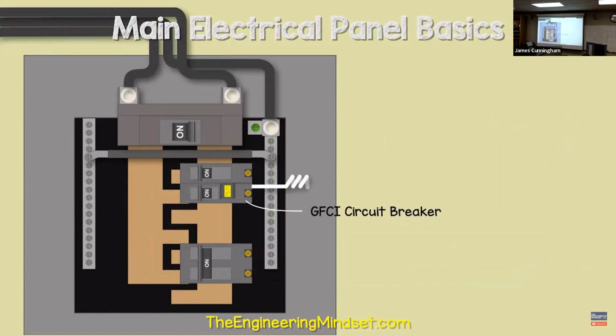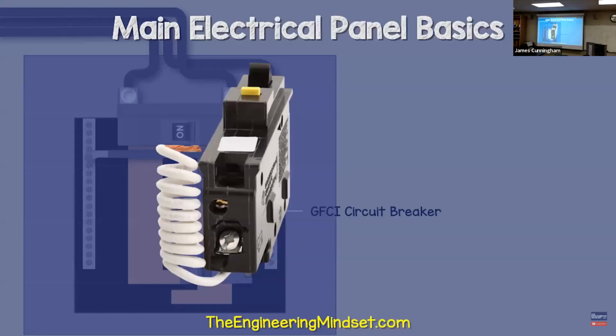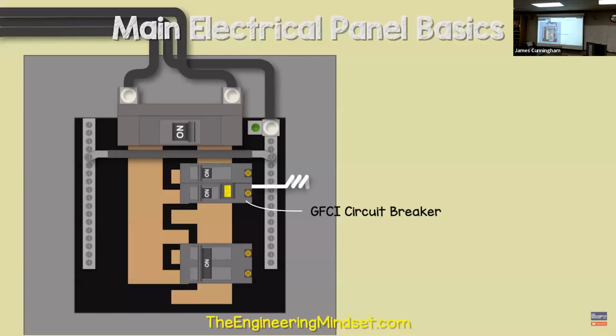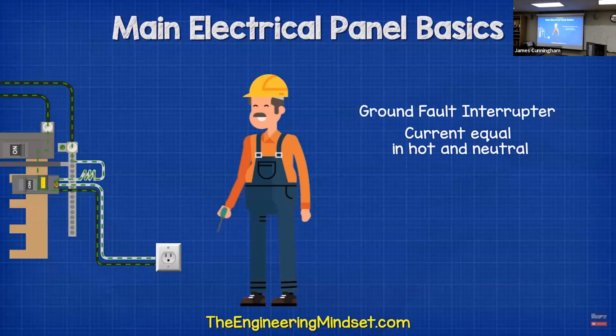We will also very likely find a GFCI circuit breaker, which stands for ground fault circuit interrupter. This will look something like this, and depending on the model you buy, you will usually have a pigtail neutral wire connected to it. GFCIs are required on certain circuits where outlets are used for places like kitchens, bathrooms, hot tubs, etc. You should check with the National Electric Code for exact details. The GFCI breaker has both the hot and the neutral flowing through it. This way it can measure the current flowing through both wires and ensure they are equal.